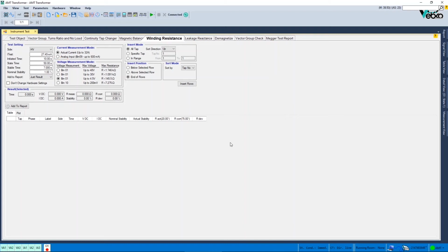Due to the fluctuation in voltage and DC current during this time, the measured resistance has a lot of fluctuations. Since resistance measurement must happen in a situation with the least voltage and DC current fluctuations, the maximum allowed fluctuation of the impedance and the shortest time during which the measured impedance needs to fluctuate below the nominal stability values are specified in the nominal stability and stable time fields respectively.